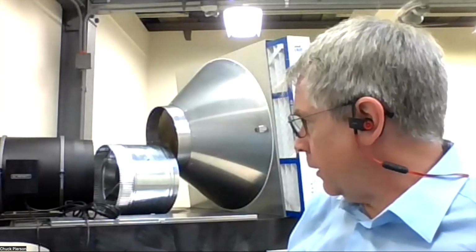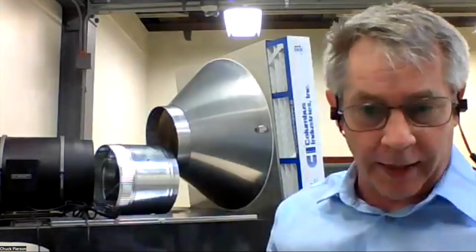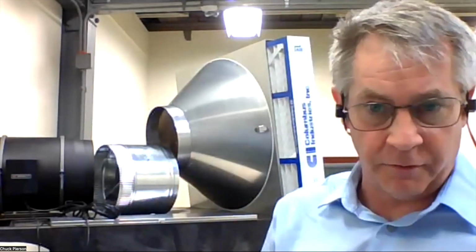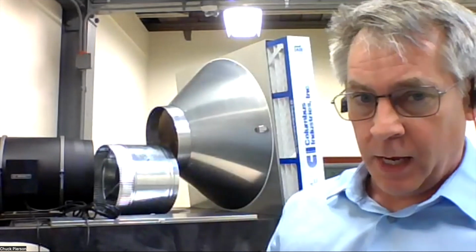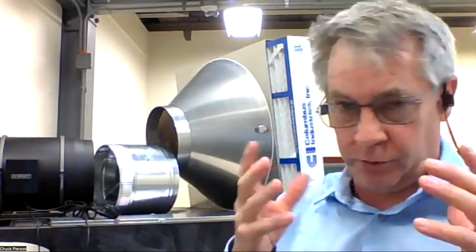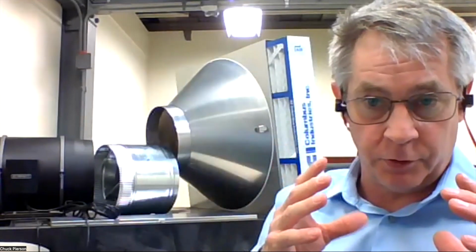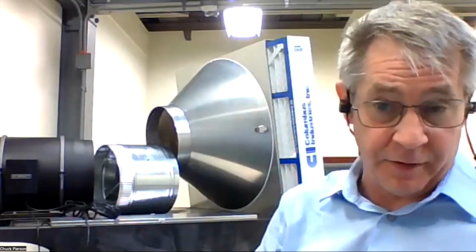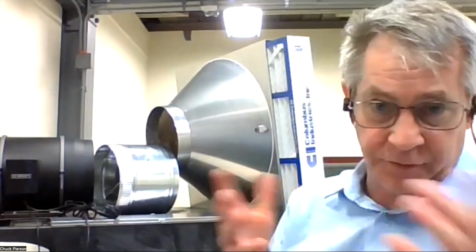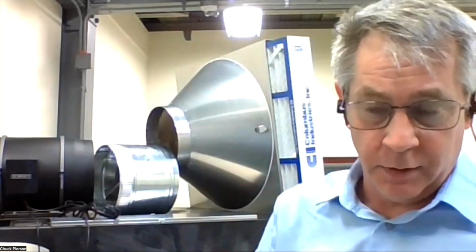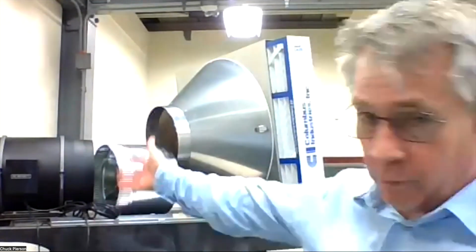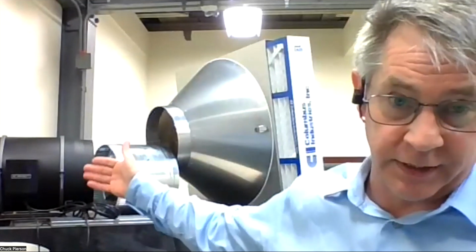We had part of this, the whole idea here is we want to have something very small and modular, but also very affordable and use off-the-shelf parts. And we were looking at using a little 6-inch diameter fan, which only did about 400 or 500 cubic feet per minute, which I think was going to be fine for this version 1. But the 8-inch fan did about 800 CFM, and it was only a few dollars more. But then for only a few dollars more, we get this 10-inch fan that can do 1,200 CFM.